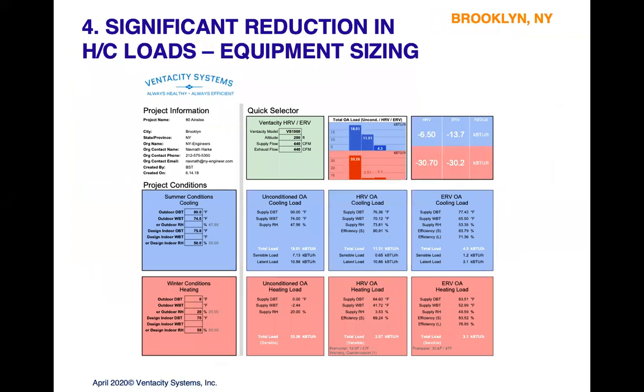And this just gives you an indicator. This is our selection tool for Ventacity. And what you'll see here is we put in the summer and winter design conditions, and then you put in the model number and the airflows, and it will give you your outside air load, the total outside air load unconditioned, and then the HRV cooling and heating load, and the ERV cooling and heating load. And you'll see where there's a little trade-off. On the HRV, you have a higher cooling load, and the ERV has a slightly higher heating load. And that's typical of a trade-off between HRVs and ERVs. But the resultant total load reduction is very, very significant here, and that has a huge impact.